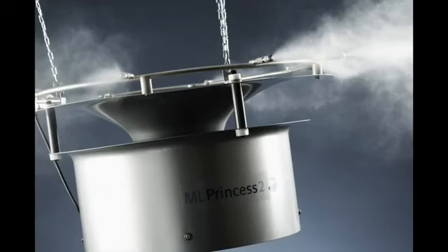Next, there are spray humidifiers. These are ideal for large areas when humidifying directly into a room. They can give up to 750 kilos per hour from a single system, but can also be used inside an AHU with lower outputs. And they do offer an added benefit of cooling alongside humidification. In fact, any cold water humidifier will do this for you.